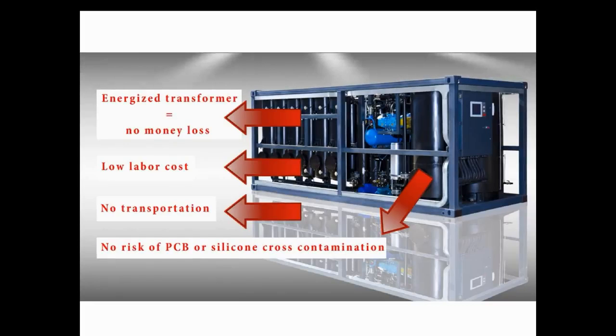To fill a transformer with new oil, vacuum should be pulled for 2 days, and only then can it be energized. It would also be a risk for the environment, should the oil spill into the ground. So, what's cheaper? To organize all mentioned above or to have at least one oil regeneration plant? The answer goes without saying.